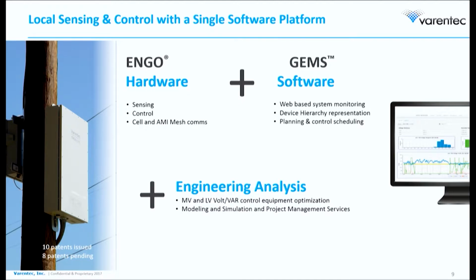This is also to give you a flavor of what the solution is really about. The core component is the hardware device you can see on the screen, with very high resolution sensing and sub-cycle control, and it basically tries to maintain the voltage to the set point you give it. On top of that, there's a software platform that does analytics and diagnostics on these units. These units talk to this software platform either via cellular connections or via AMI mesh networks.